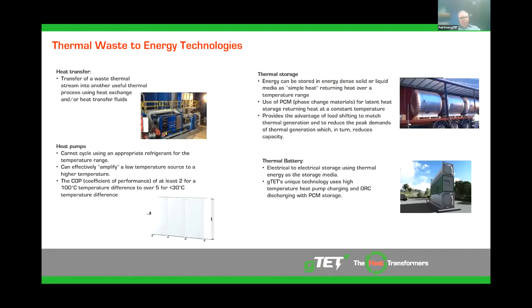More than 50% of the world's energy is used in thermal applications, and close to 50% of that is used in industrial thermal systems. Low-grade heat, which we categorise as less than 200 degrees Celsius, wasted from industrial processes, has often proven challenging to economically utilise, but can provide a significant opportunity in thermal waste-to-energy projects. Often waste heat streams can be utilised by simple heat transfer, as someone just went through before, such as changes in medium, for example, exhaust to water, or even cleaning up the waste stream, for example, exhaust to clean air.